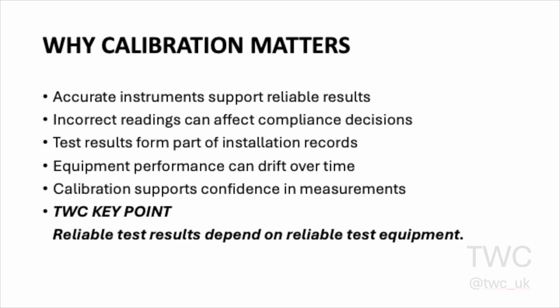Test results are used to demonstrate compliance with standards, regulations and scheme requirements. Whether we're measuring electrical parameters, gas combustion performance or technology specific values, decisions are often made based on the readings obtained from test equipment. If an instrument produces inaccurate results, the quality of those decisions may be affected. Calibration helps provide confidence that measurements are reliable and that the evidence supporting compliance can be trusted.